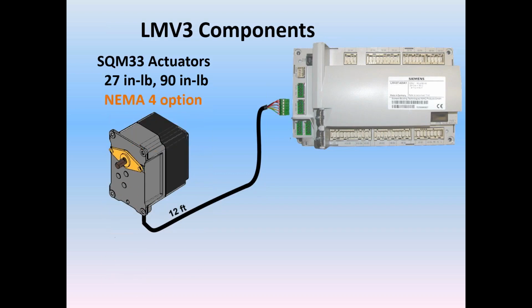And you can also add NEMA 4. The entire motor is NEMA 4 with the exception of that shaft, and on that shaft you can put a NEMA 4 kit, and that puts an O-ring on the shaft, and now the entire assembly is a NEMA 4 rated assembly, the cover, the cord, and the shaft.